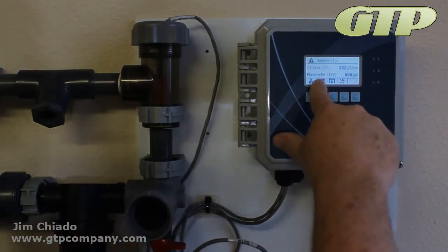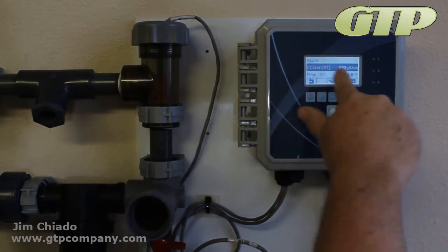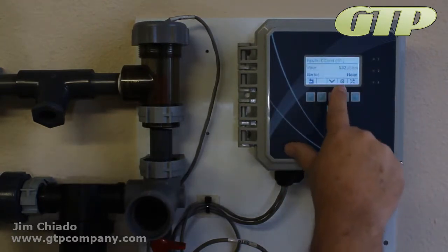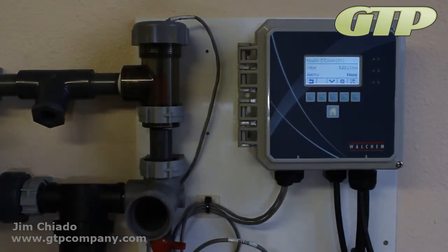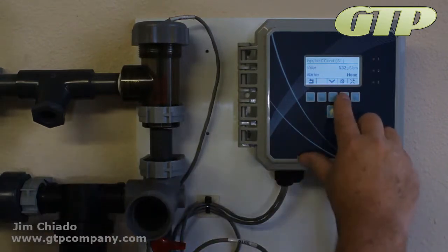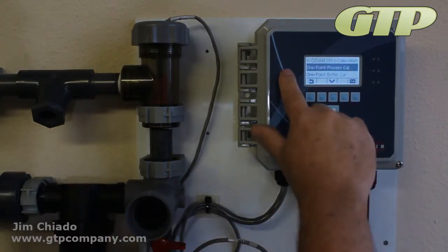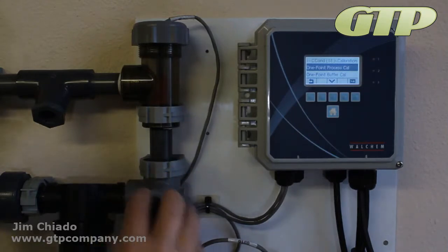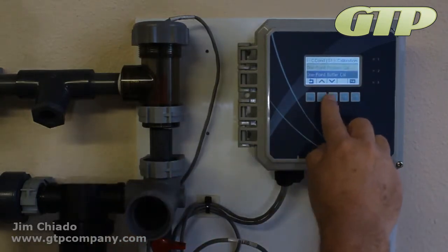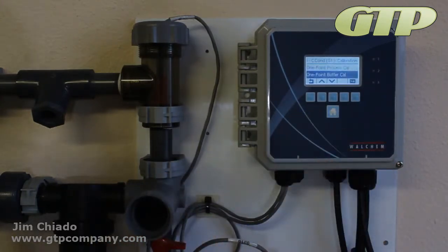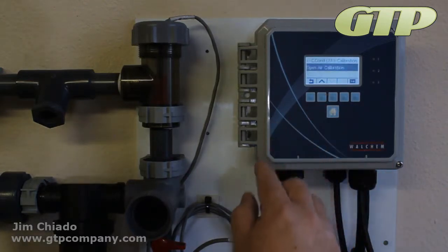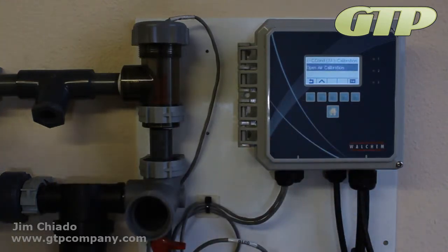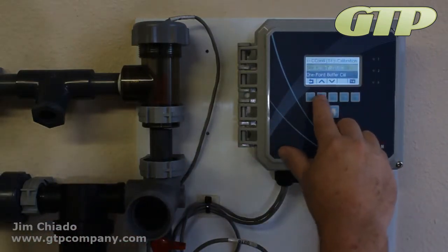So we're going to go to Inputs, Conductivity, and now we get the crosshairs. We get the calibration button. So we're going to pick calibration, and you can see this 1-point process, which is basically the process water that we have here. A 1-point buffer, if we had buffer solution. A 2-point and an open air calibration. Open air calibration should be 0 or 1. It should be almost nothing. And we can see that it was working there.